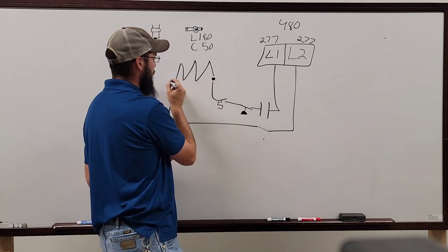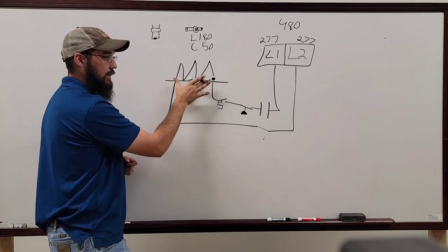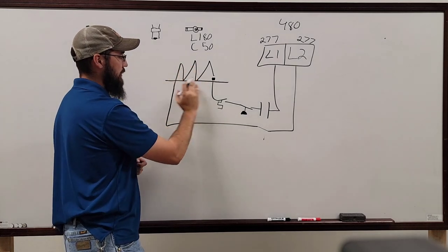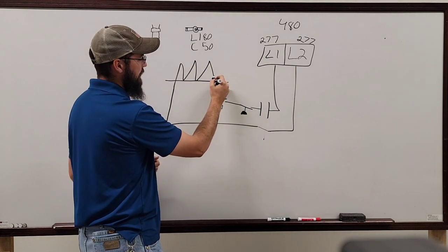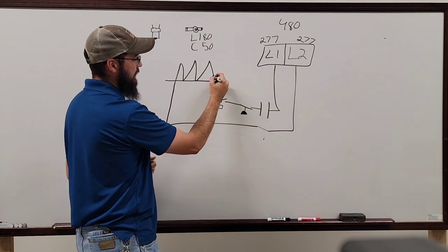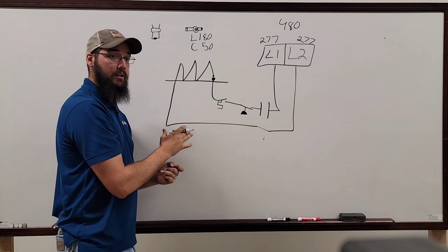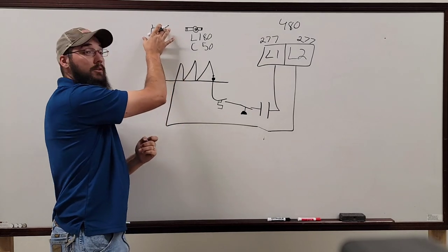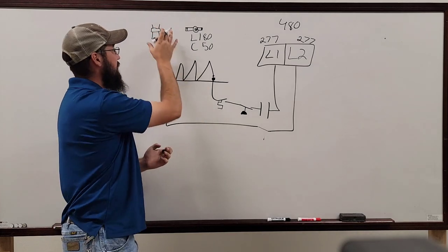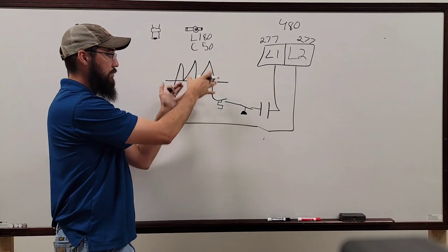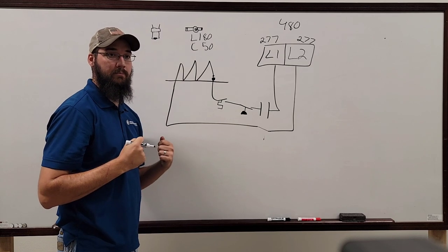The really old school ones, they would be right here, right as you're coming through your plates inside of your panel. So this is your electrical cover plate, right? It would be right here on the other side, and it'd have a nut here and a nut here, and the little string would go there in the middle. That's where those used to be mounted. As time progressed, we eventually upgraded to putting them in ceramic, and this made them a lot more reliable and easier to change. With these, you could do it without having to pull the whole heat kit. When they were the old style, you had to remove that entire heat kit every time.